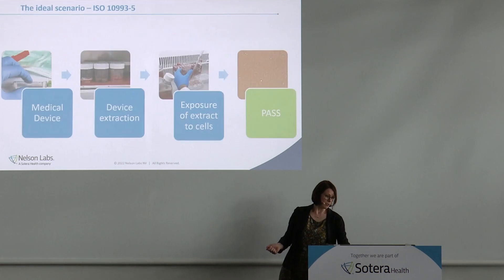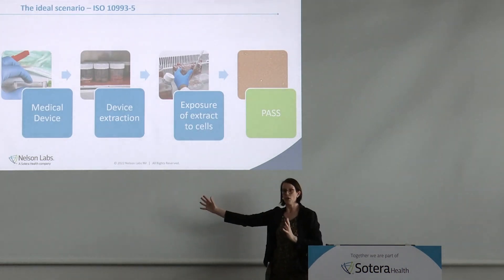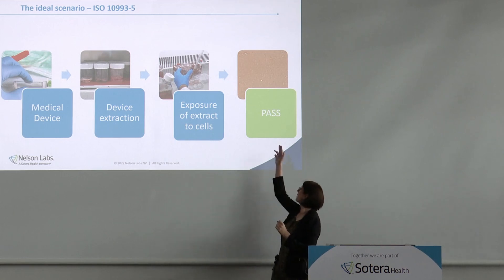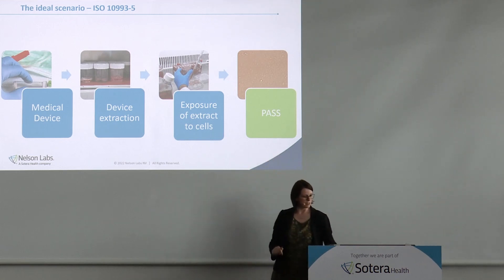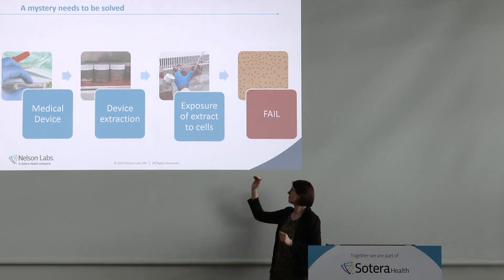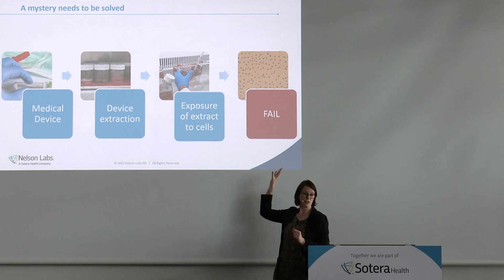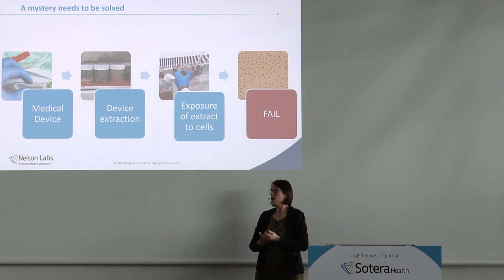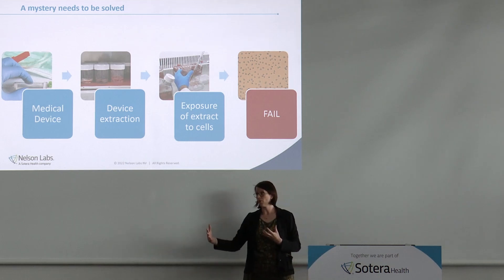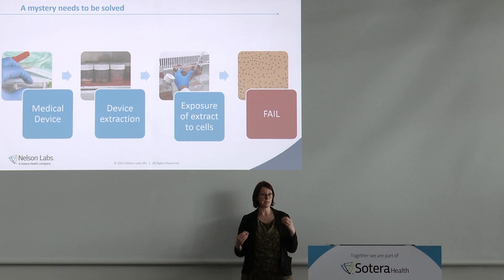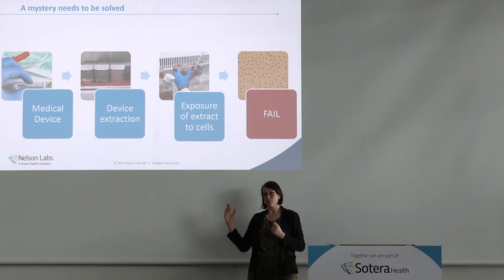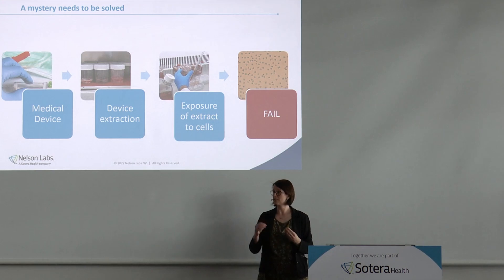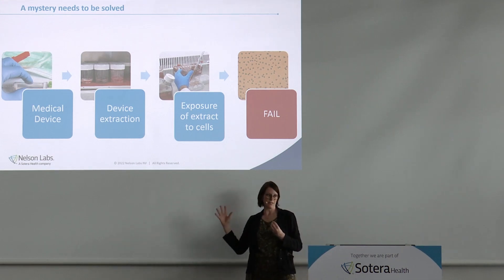Now for a mystery: normally in the ideal scenario, you have your medical device, you extract it, you expose the extract to the cells, and you see happy cells — green light, pass, the cells are alive. Today's mystery is: you have your medical device, you do the extraction, exposure of the extracts, and the cells are dead — black dots, a fail. This often causes panic at manufacturers and sponsor sites, because they believe this will stop their submission. But ISO 10993-5, which describes the cytotox test, says there is a potential cytotoxic concern and you have to investigate it — but that does not mean your device is unsuitable for its intended use. It's just a warning sign.